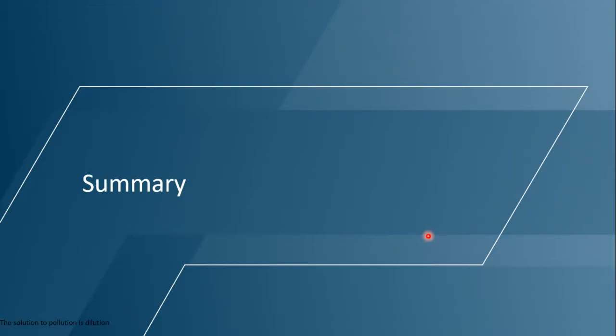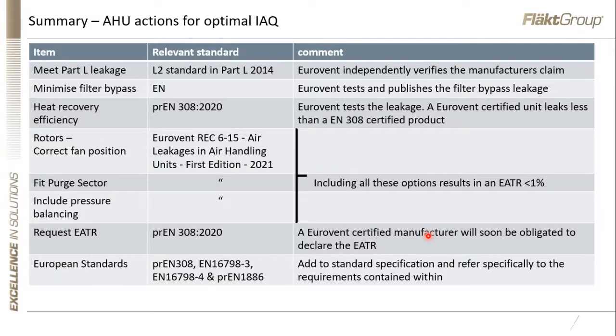So just a quick summary of all that. If I was a consultant, and I'm not, I would be looking to implement in my standard specification all the relevant information that limits the leakage within an air handling unit. And I would enshrine that in, like I say, in my standard specification. So this is, if you like, a checklist. If you are a consultant and you want to do that, you need to meet Part L leakage. L2 is the standard in Part L. Eurovent independently verifies the manufacturer's claim. You need to minimize the bypass leakage.